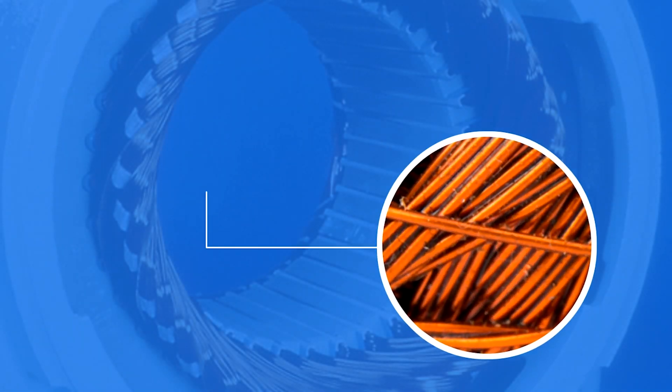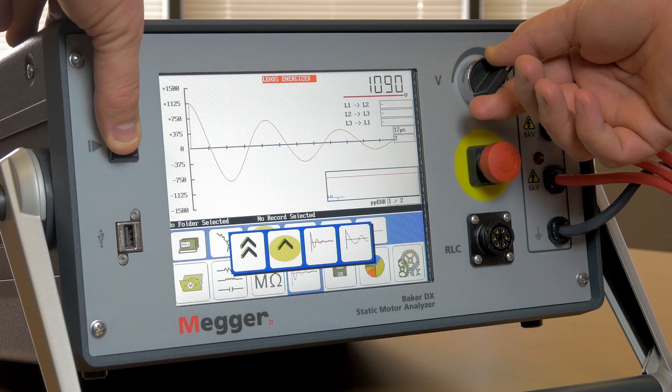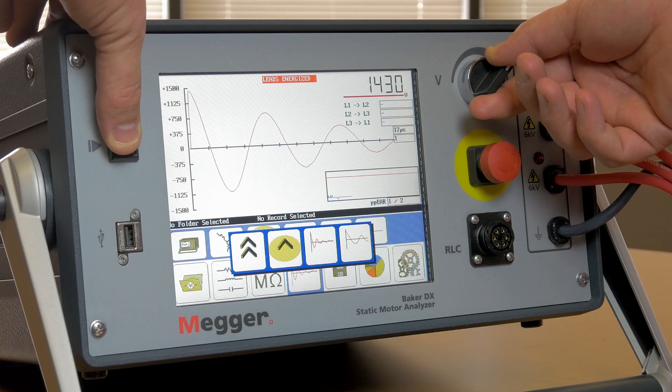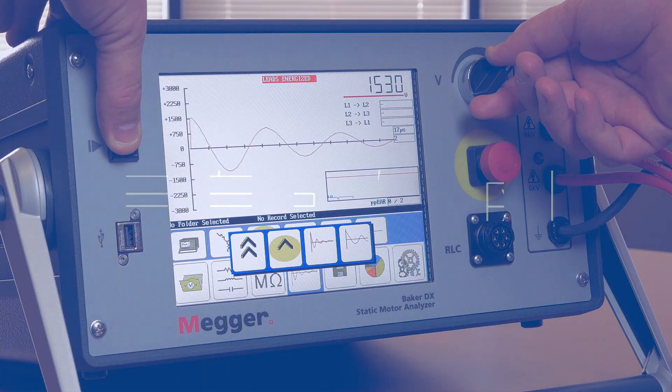The most common insulation fault is a turn-to-turn insulation failure. A surge test is the only test that can find turn-to-turn insulation weakness and failures. Let's look at how a surge test works.